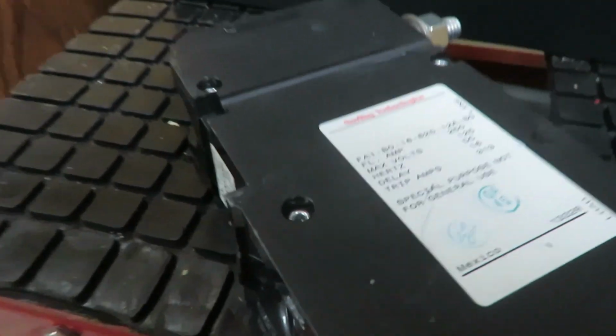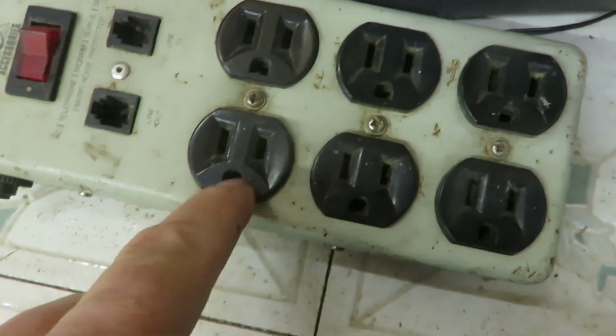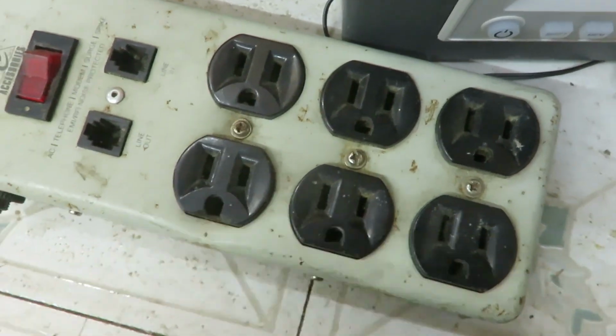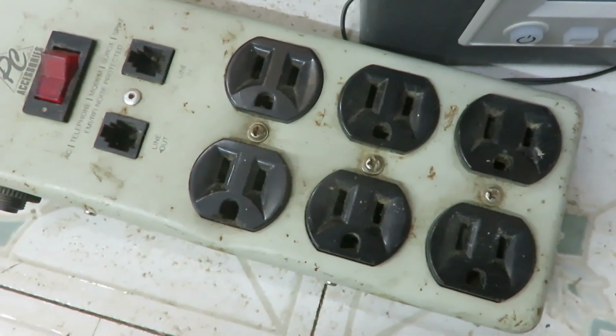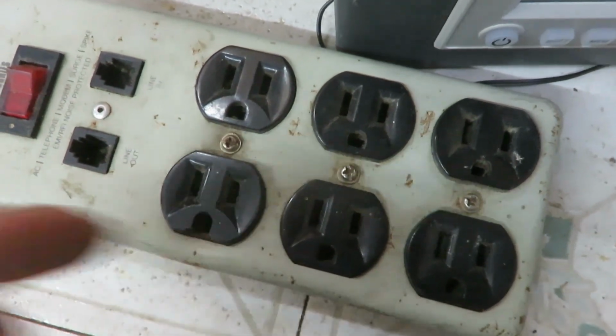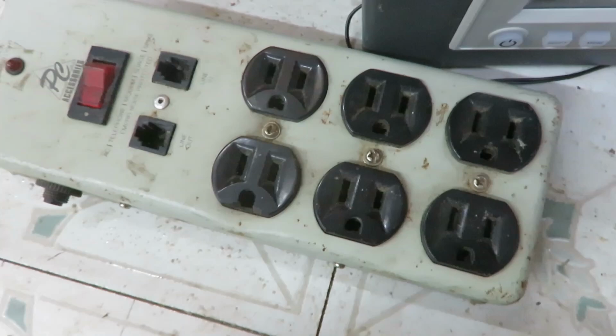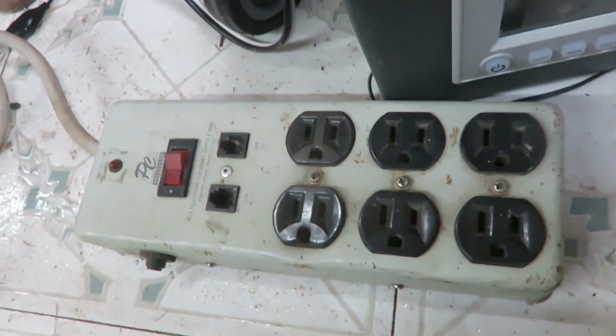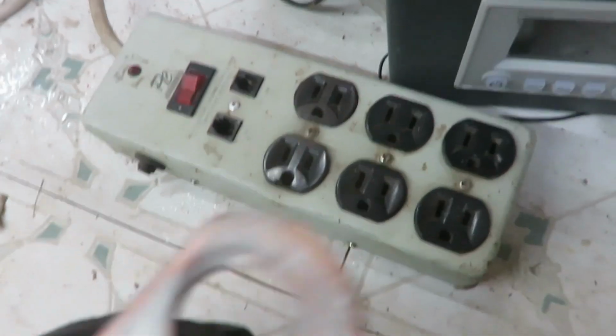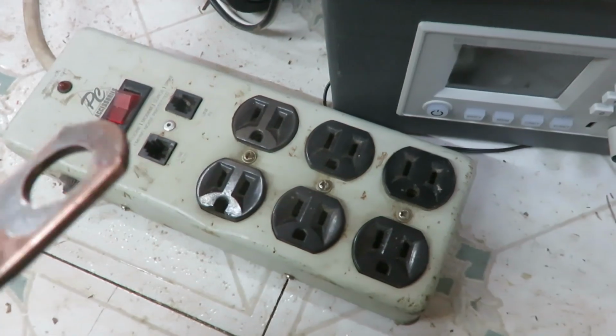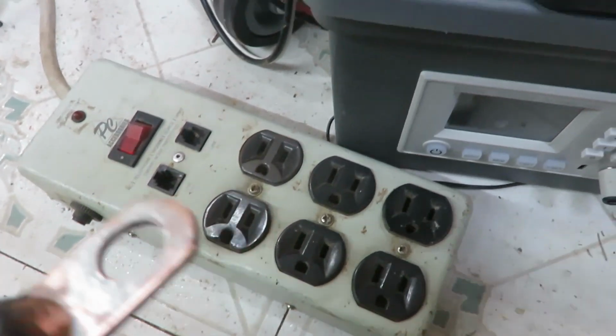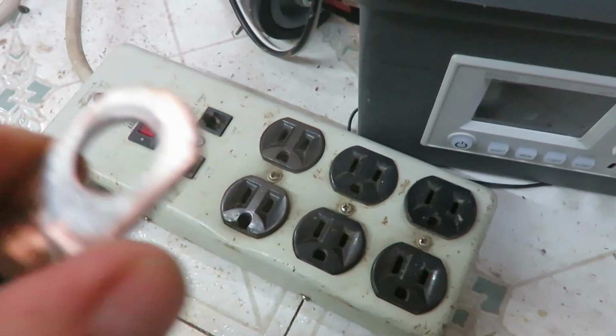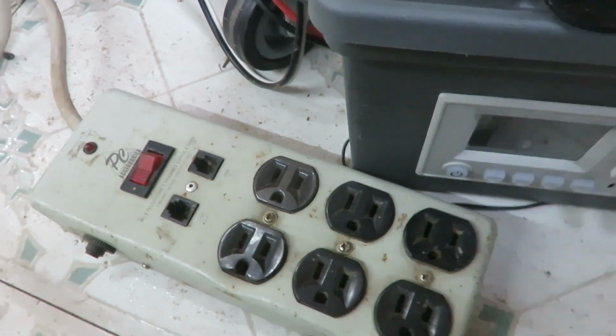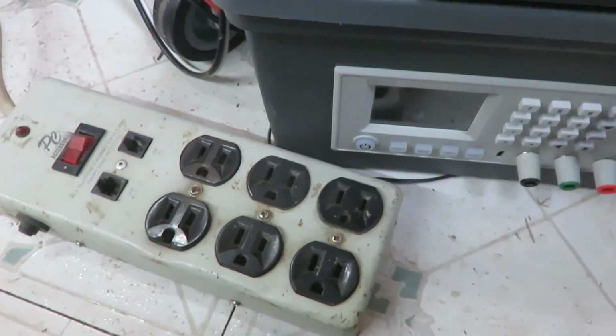We don't worry about things like 120 volts as much, because at 120 volts the resistance on a bad, oxidized copper connection isn't as significant. Ideally they'd be clean regardless, but when you're down at lower voltage, like 12 volts, you want to make sure they're really clean for your best power. Otherwise, if you get high resistance and a lot of power, they're going to warm up and melt things if it gets warm enough.